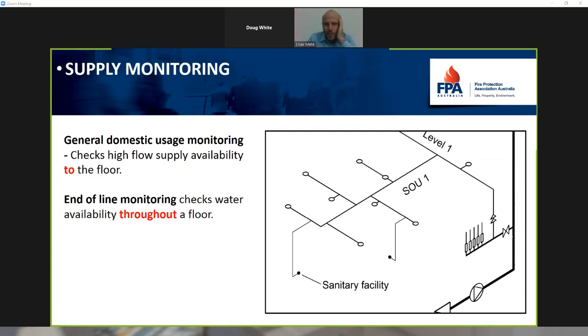The end of line monitoring is the toilets, the sanitary facilities here. So that's at the very end of line. Every toilet in the building needs to be connected to the sprinklers, which means that no matter where you are in the building, if someone were to, for example, cut the line here at the feed down the corridor, or it's a part of a corridor to do renovations, no toilets would work in that area downstream. So it's kind of monitoring just at the very ends of the system.